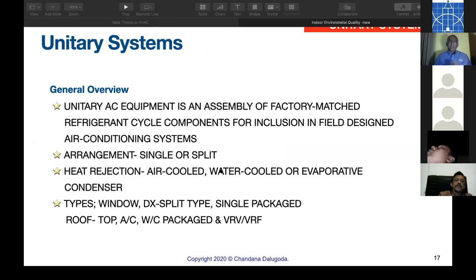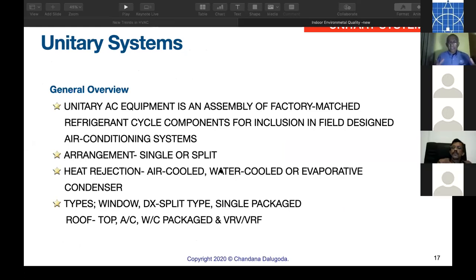Finally, the fourth system called unitary systems. Now, unitary means the AC equipment is a complete assembly of factory matched equipment. So that means our cooling load calculations, our sensible heat ratio, all that is entering living conditions, we cannot perfectly match because it is factory matched equipment. The arrangement of unitary systems can be either single or split into two. Now, heat rejection: air cooled, water cooled, or evaporative condenser, various types, either window type, split units, the correct word is DX split, direct expansion split type, single package rooftop.